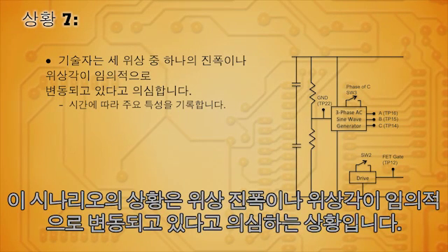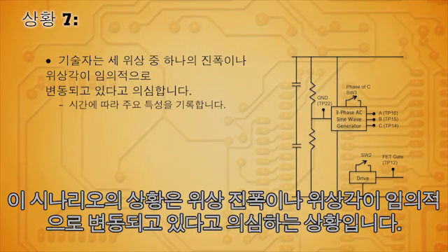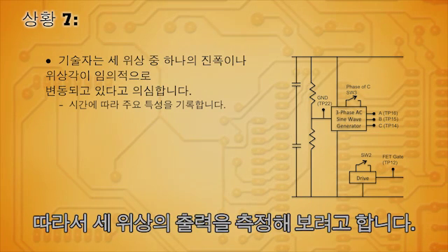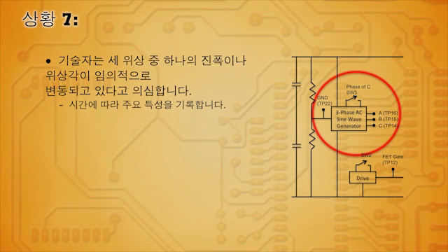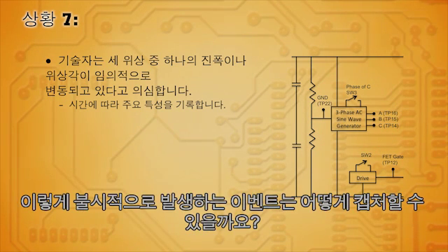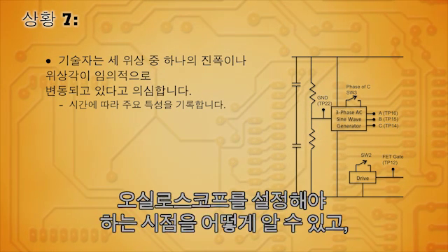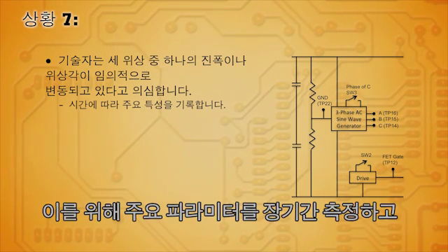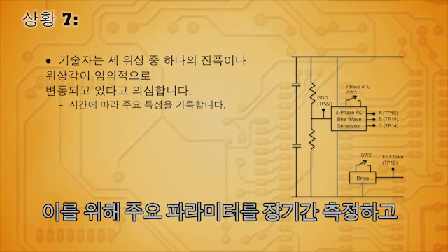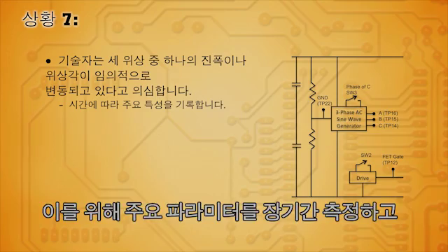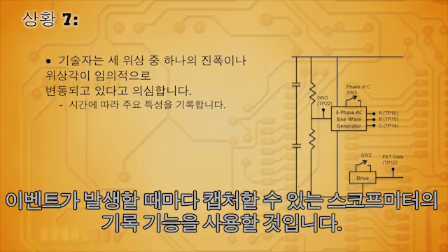In this scenario, we suspect a phase amplitude or phase angle is randomly changing, so we're going to measure the output of the three phases. The problem we'll be trying to solve happens randomly. So how do we capture that event? How will we know when to set up the oscilloscope and be sure we're watching when the event occurs? For that, we'll use the scope meter's recording capabilities to measure our key parameters over a long period of time and capture the event whenever it happens.